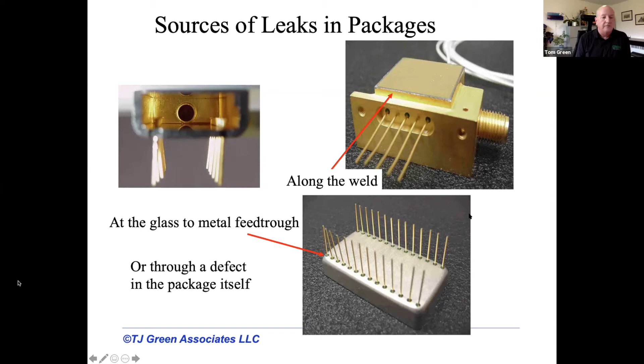But in an RGA, if you found moisture, the moisture may have been in there at time 0, or it could be high moisture because of a high leak rate. And one thing you have to keep in mind is most epoxies, polyimides in particular, any kind of circuit board, some implants are just advanced SMT products that are put in there. Well, they all just in room ambient absorb quite a bit of moisture, in some cases 1% to 2% by weight. And if you do the molar conversion of that inside an enclosed package, a 10 cc package, let's say, that's a huge amount of water vapor that's potentially going to be outgassed, and you have to worry about it. In rare cases, you can have some other things going on that generate moisture.